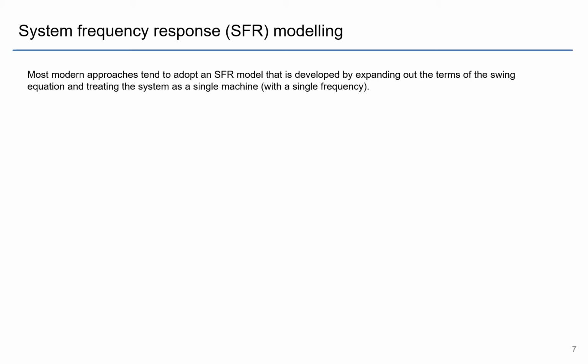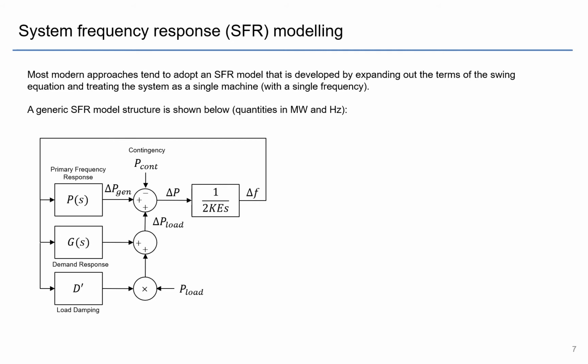We've largely moved away from using simple catch-all metrics like that parameter K, and most of the modern SFR models are now developed based on expanding out the terms of the swing equation and treating the system as a single machine with a single frequency. So you often see the terms single frequency model or single mass model also being used for an SFR model. So the generic structure of an SFR model is shown below, and these quantities are in megawatts and hertz. They could also be in per unit, but this is structured in natural quantities. And you have here the inertia model from the swing equation, and here's all the parts that form the delta P part. So this is really just the inertia model here, with load damping then stuck in external to the inertia model. So in some models, the damping factor is included in this block, as we'll see later, but you can also include it externally through load damping as a part of the change in active power.